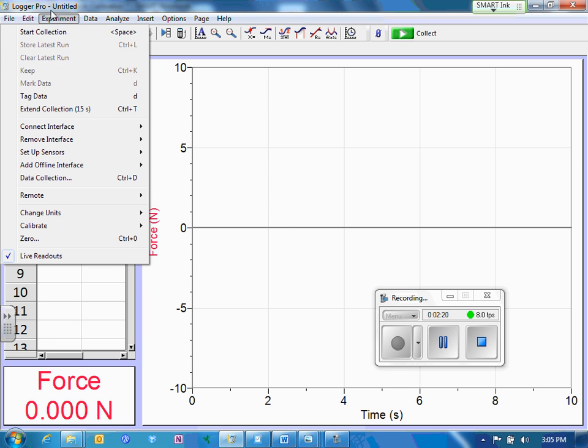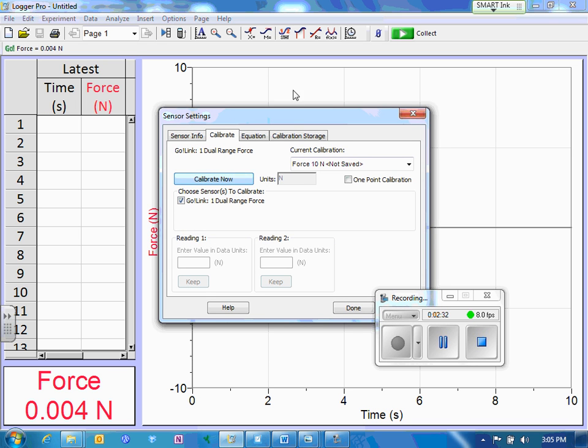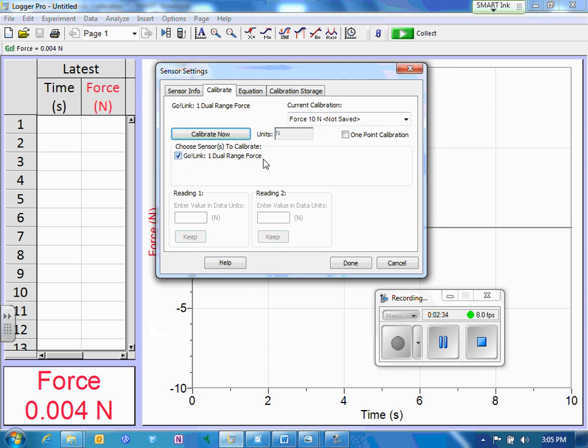The next thing we're going to do is calibrate it, so we want to go down to the experiments file to calibrate. Then we select the dual range force sensor, and this brings up the calibration screen. We're going to do a 2-point calibration. The first point will be 0. We have it set up right now at 0, so I hit calibrate now, click, enter the value of 0, wait a few moments, and then hit keep.